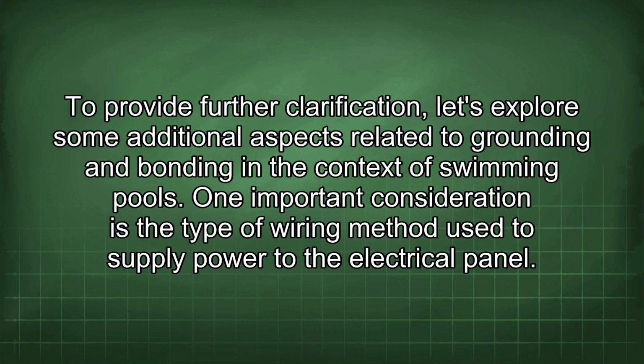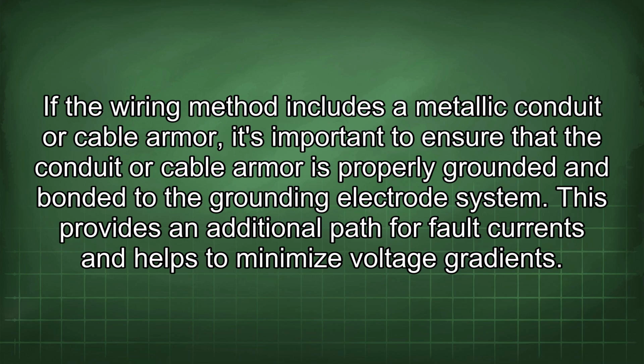swimming pools. One important consideration is the type of wiring method used to supply power to the electrical panel. If the wiring method includes a metallic conduit or cable armor, it's important to ensure that the conduit or cable armor is properly grounded and bonded to the grounding electrode system. This provides an additional path for fault currents and helps to minimize voltage gradient.